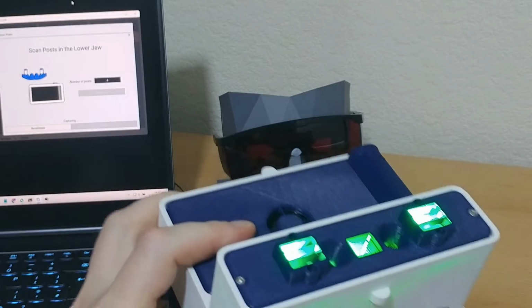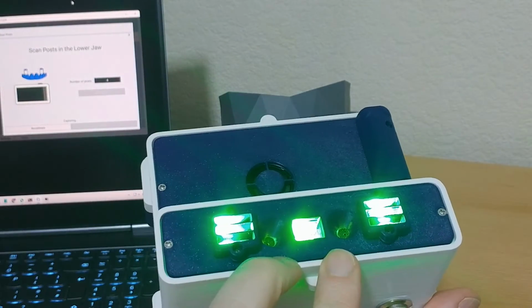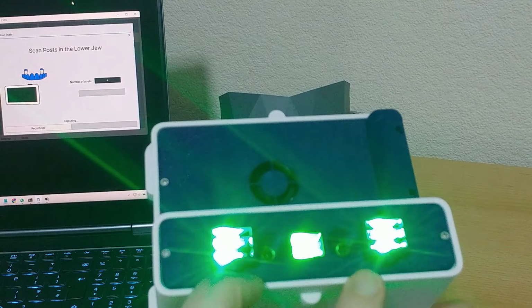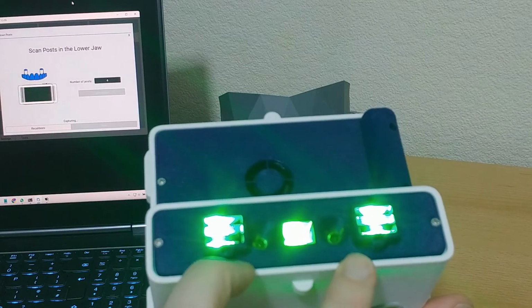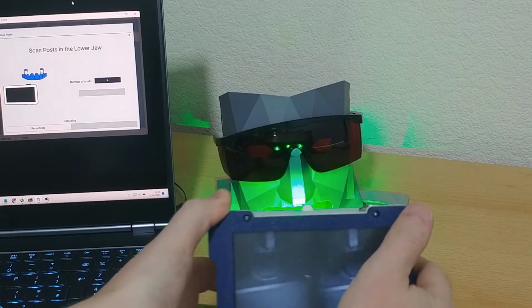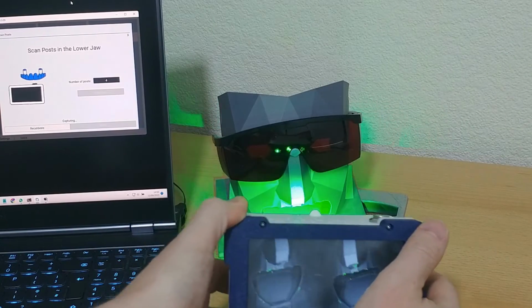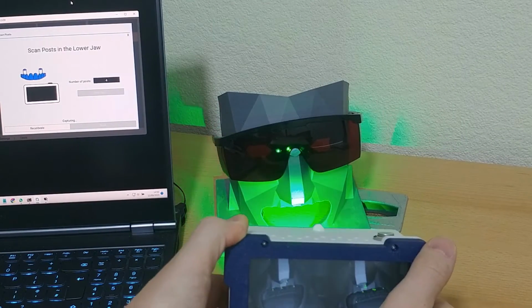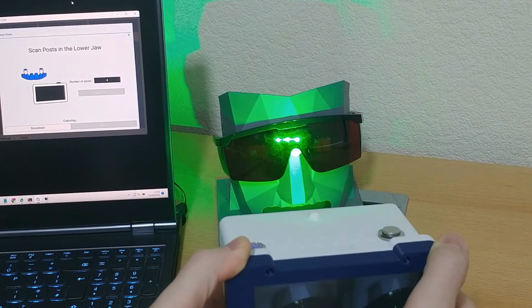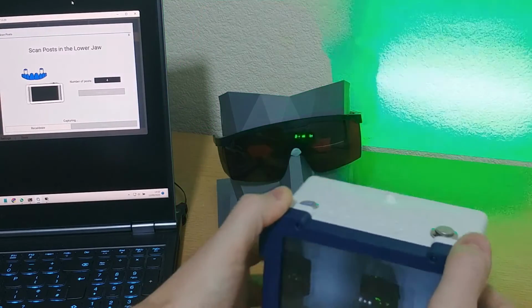Okay, now let's have a look at the scanner. We have two cameras to make the 3D measurements and some super bright green LED lighting to light the posts up. They are bright enough that if you intentionally stare at them, they may be harmful to your eyes. You shouldn't do this. But if your patient is sedated, or even if not, the red glasses block the light and make it safe and comfortable.